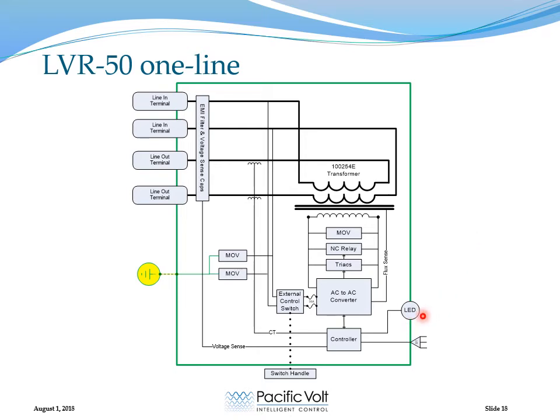There's an external LED that's used as the first line user interface. So if the LED is on, the regulator is functioning and regulating, and if it's blinking, it's in a fault condition. And if the LED is out, that means the control board has had a failure or one of these fuses has blown.